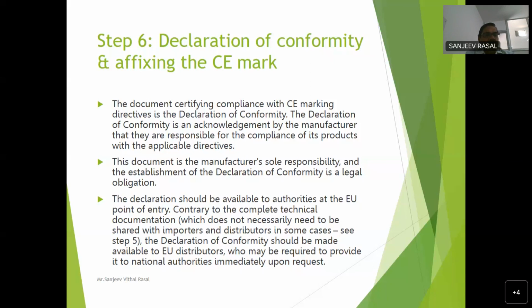The declaration should be available to the authorities at the European point of entry. So in whichever country it is entering, at that point it should also be available. If the route of entry differs, then it may be different. So at that particular point of entry, a copy of the technical files and documentation should be available. Contrary to the complete technical documentation, which does not necessarily need to be shared with the importer or distributor in some cases, the declaration of conformity should be made available to the European distributor, who may be required to provide it to the national authorities immediately upon request.